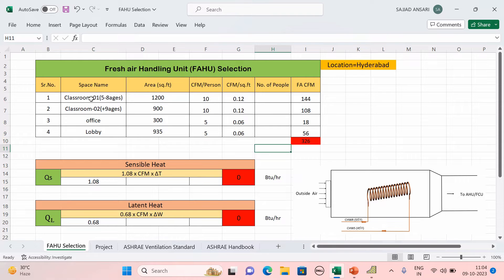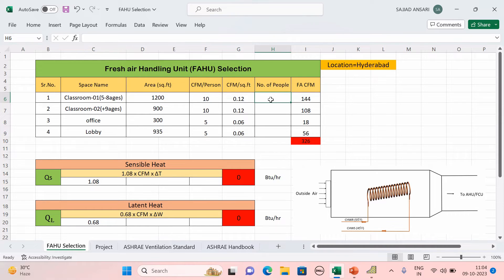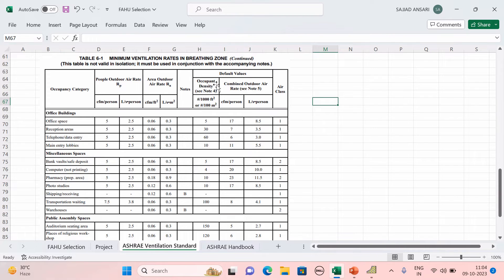Next we need to find out the number of people. The number of people is determined from the furniture layout. If furniture is not shown in the layout, ask the architect or interior decorator. Otherwise, use ASHRAE ventilation standards — the occupant density is also given there.